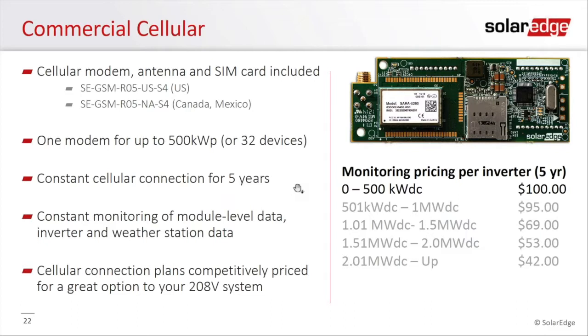Call it the primary inverter. Okay, and this one modem is good for up to 500 kilowatts DC of your project. So, as per the poll that Mike just took, it seems like 70–80% of your 208 applications are well under that. So this should be enough. One modem would be enough for all of your 208 applications.